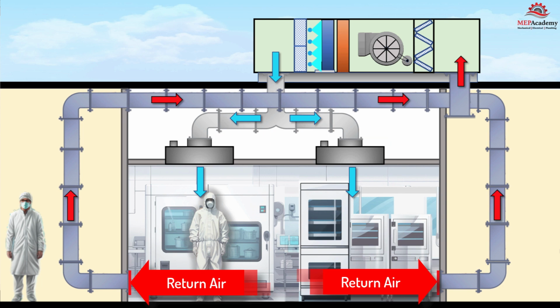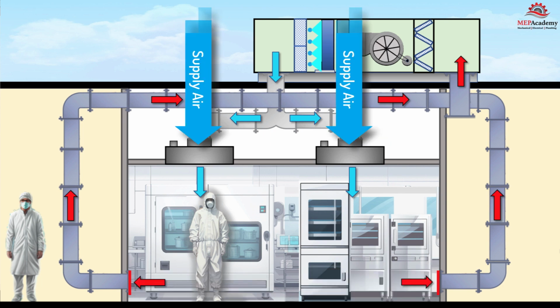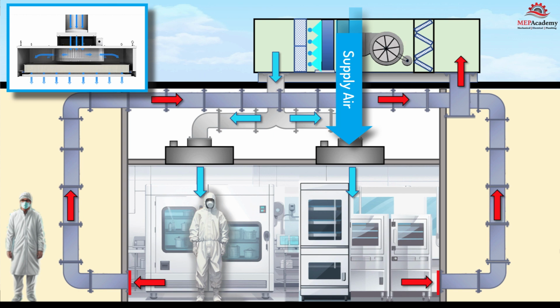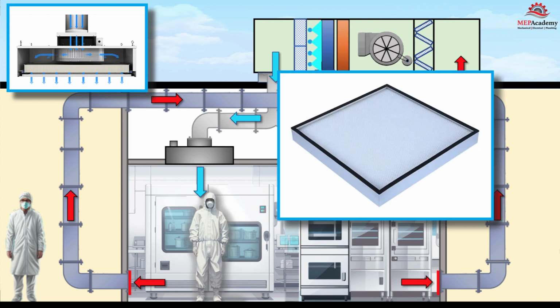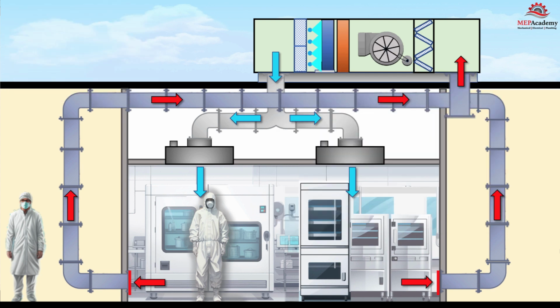Filter. The air passes through a high-efficiency filter such as a HEPA or ULPA filter within the fan filter unit housing. These filters are designed to remove particles as small as 0.3 micrometers, HEPA, or 0.12 micrometers, ULPA, with high efficiency. They capture airborne contaminants including dust, pollen, bacteria, and other particles, ensuring the air leaving the FFU is clean and free from harmful substances.